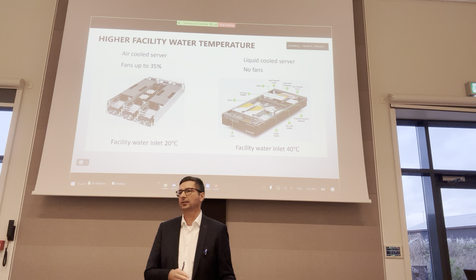Now I'd like to show the whole picture. On the right-hand side is what we all know: at the moment, 99% of all data center sites are still air-cooled. As Mario said, liquid cooling is still a niche, but we're confident the tipping point is close, and when it happens, with all these AI applications, it will scale big time. In this slide we compare 130 air-cooled racks versus 26 liquid-cooled racks providing the same compute.